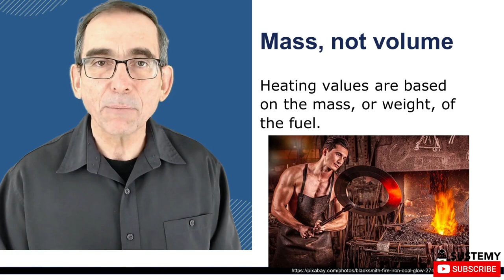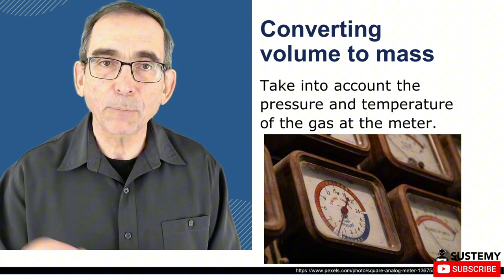Finally, remember that heating values are based on the mass or weight of the fuel. If you are using natural gas or another gaseous fuel, which is often metered by volume, you will need to take into account the pressure and temperature of the gas at the meter. As gases are compressible, you need to know both the temperature and pressure in order to calculate the density and thus the energy content. Now, some gas meters have inbuilt pressure and temperature compensation and show the volume delivered at standard temperature and pressure, or STP. And the gas supplier will often provide a heating value based on volume at STP. It's important to know if your meter is STP compensated or not, and if not, that you take this into account when calculating the volume that would be at STP.